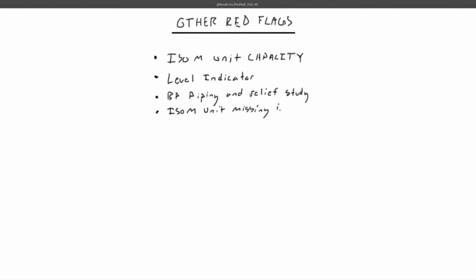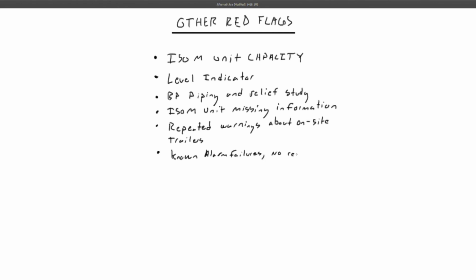Trailers have been periodically sited in and around hazardous process areas for reasons of convenience, such as ready access to work areas. Key alarms and level transmitters failed to operate properly and to warn operators of unsafe and abnormal conditions in the ISOM unit. Written startup procedures for the raffinate splitter were incomplete. Texas City Refinery experienced 2 fatal safety incidents in 2004 and a serious furnace fire.